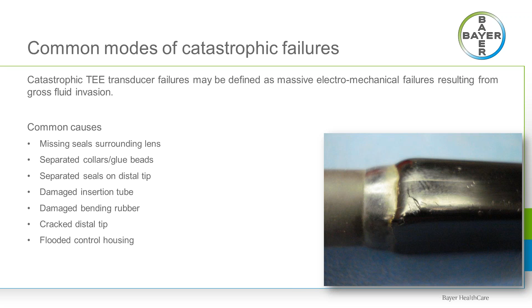Probe manufacturers are pretty clear in detailing which portions of their probes are and are not able to be exposed to fluid, as well as which sections are submergible. Another popular mode of failure is fluid invasion to what we call the control housing. Once fluid enters this area, that fluid is free to migrate to any interior portion of that probe. We've seen probes that have been fully flooded the whole way from the tip to the connector. We've had fluid and disinfectant dripping out of the connector pins.